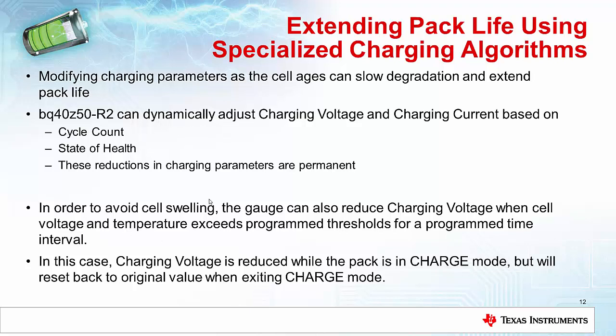We've also got a technique for avoiding cell swelling. So basically it's looking at when you have a cell at high voltage and high temperature for an extended length of time. If you end up with elevated temperature and high voltage over a long period of time, then it will go in and reduce the charging voltage in order to reduce the amount of heat that's being generated from the charging. This one is not a permanent reduction in the charging voltage. This will be maintained as long as you're in charge mode, and then as soon as you exit charge mode, the settings for the charging voltage will reset back to the original levels.